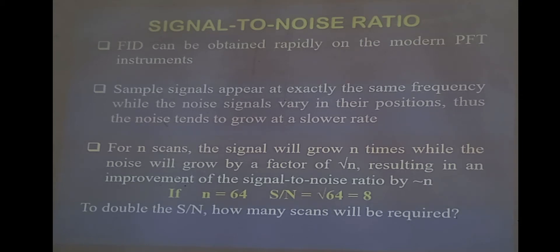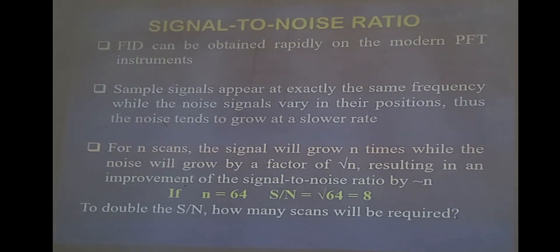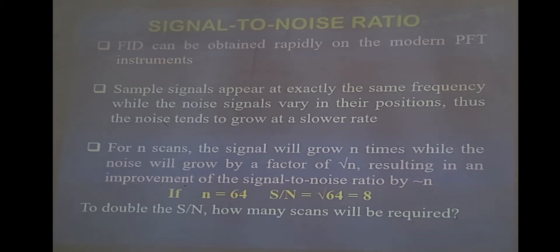The good thing about this pulse Fourier transform technology is that you can scan a molecule rapidly. Within no time you will have a spectrum. As we have discussed earlier, the resonance or excitation, acquisition of the FID, and the Fourier transform — it takes a few seconds. Within a few seconds you can do all this, and all these steps are involved in one scan, so one scan can be performed in a few seconds.